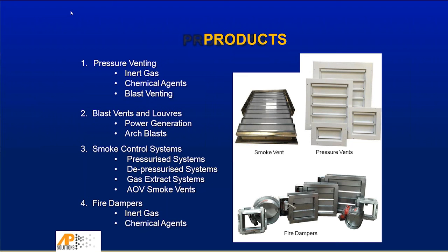That also links into the consultancy service, which has tended to be more looking at issues where systems have failed. The walls have been blown over, ceilings have been lifted, and over the last 5 years, certainly, we've probably looked at about 10 systems around the UK and Europe where they are systems that have been vented, but the structure has failed due to the venting systems not being designed correctly. And that's on inert gas, and we've investigated one or two FM200 systems doing the same.